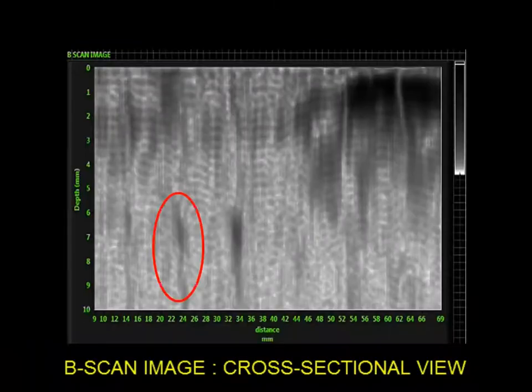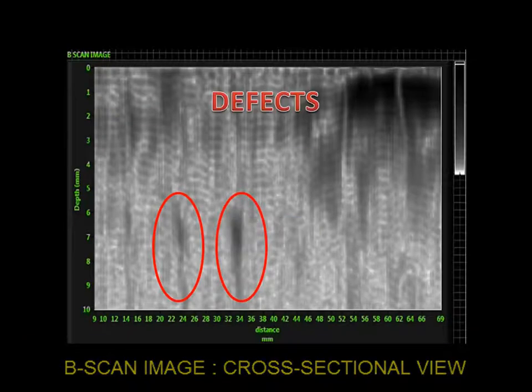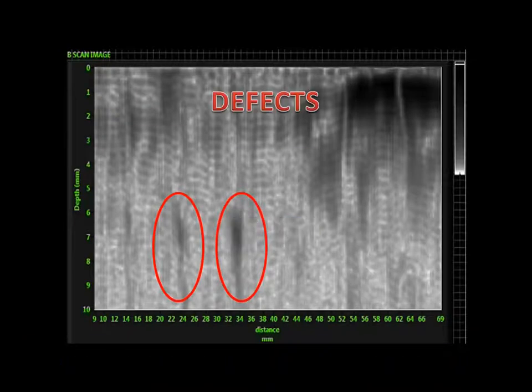The B-scan presentation gives a cross-sectional view of the material being tested and will show the length and depth of a flaw in the test material.